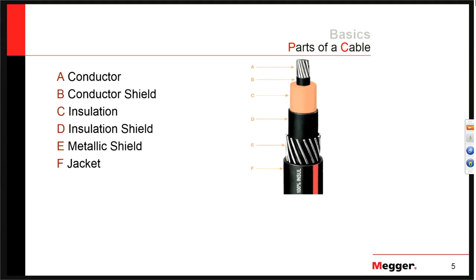The semi-conductive layer helps smooth those out and provides a nice smooth transition into the bulk insulation. The bulk insulation is there to hold the voltage back — it's typically EPR, XLPE, or many other kinds. After the bulk insulation is the same semi-conductive material to provide a smooth transition onto the metallic screen layer. Finally, there is the outer jacket, which is primarily there for mechanical and moisture protection.